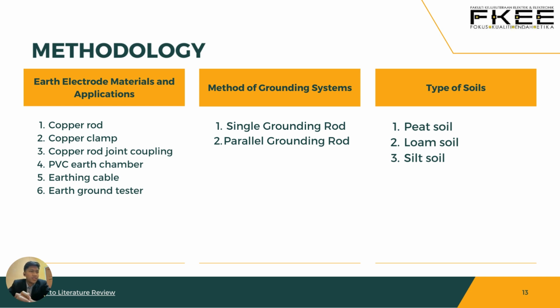Another part of the methodology involves the materials and application, such as copper rod, copper clamp, copper coupling, PVC earth chamber, earthing cable, and earth ground tester. For the method, as mentioned, I'm using 2 types: single and parallel grounding rods, and type of soil. There are 3 types of soil: peat, loam, and silt.